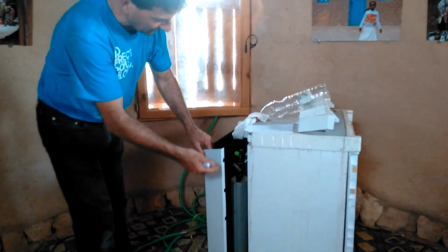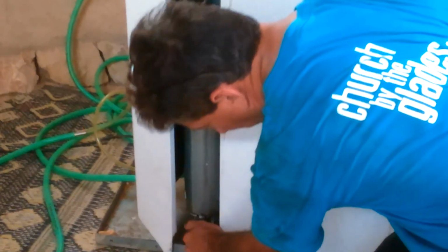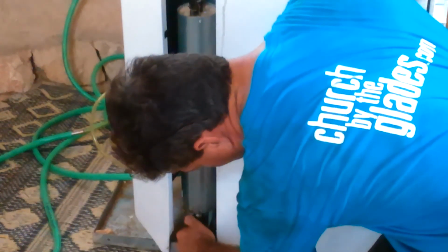The other thing we want to demonstrate is we have here a biogas refrigerator, and the biogas refrigerator is an absorption chiller, and it's very hot in here, so we were using a cloth with water that was wicking the water out of the water bottle and helping to cool off the heat exchanger. This is where the gas goes when we press on this button here and we light it down here. Then we get a little flame here. I don't know if you can see it. If you come really in close, you may be able to see the flame. And that flame is creating heat that's going up this chimney here, which is then separating ammonia and water, and then that creates the absorption chilling cycle down there.